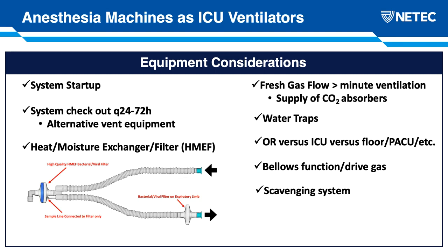We also need to make sure that in order to perform that system check we described earlier, which typically happens on power up of the device, we do it at least every 72 hours, and the recommended usual state is every 24. During that time, the machine will be completely non-functional. Different connections have to be made, purposeful obstructions have to be caused, and so because of that, when we're performing these checks, we have to have alternative ventilator equipment available.